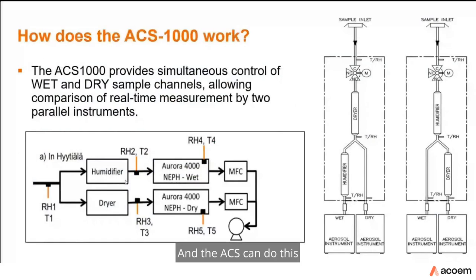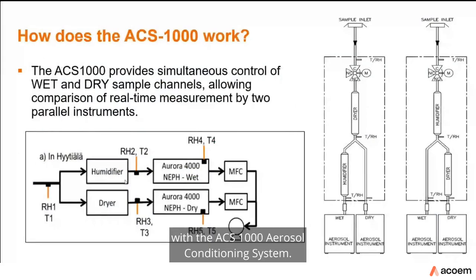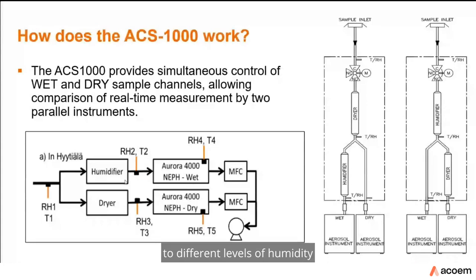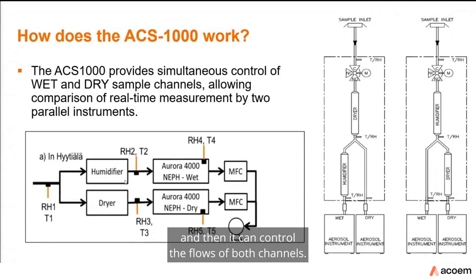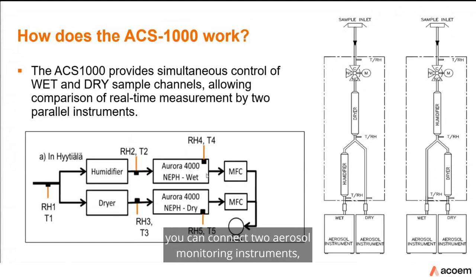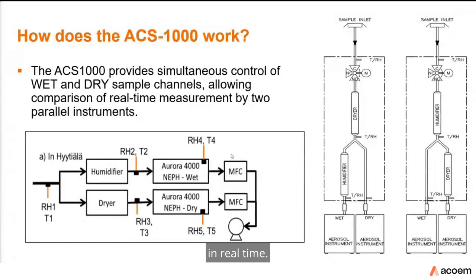The ACS can do this by simultaneously controlling two channels — a wet channel and a dry channel — with the ACS 1000 aerosol conditioning system. It controls the wet channel to different levels of humidity while maintaining the dry channel at a level usually lower than 40% humidity. It controls the flows of both channels, and at the bottom of the ACS you can connect two aerosol monitoring instruments such as Aurora nephelometers to measure scattering properties and calculate hygroscopic growth of aerosols in real time.